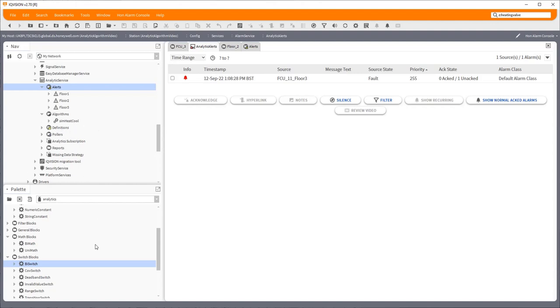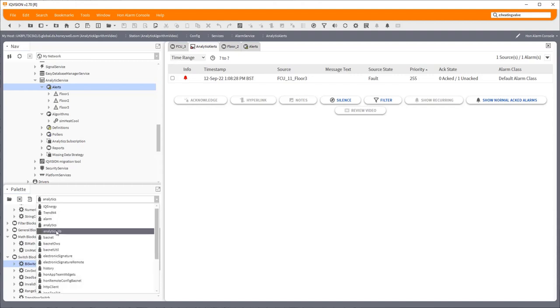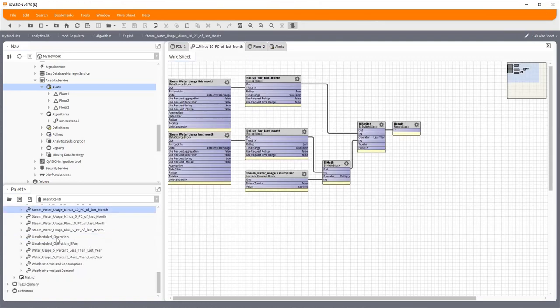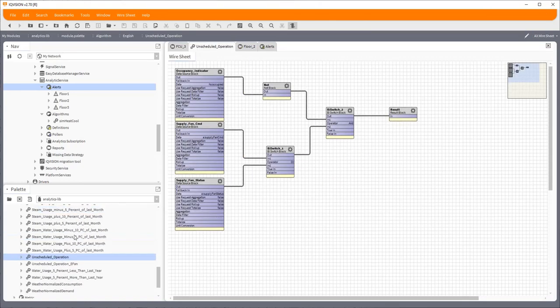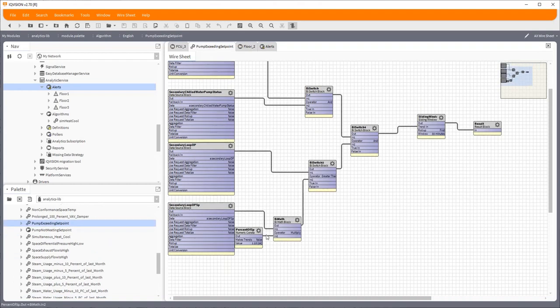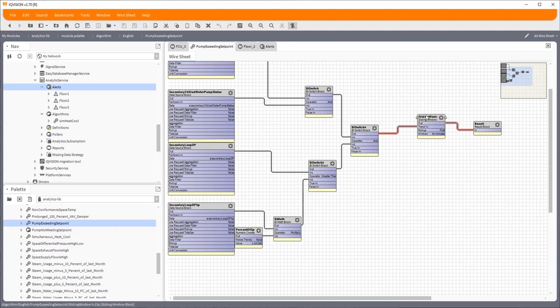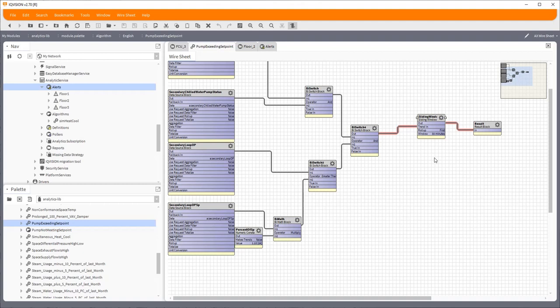So I hope that is of some use. There are some 50 odd examples in the analytics library. You can use these as you see fit. You can see how they're all assembled, and hopefully the little demo I've just given you will give you some idea as to how these pieces actually all slot together. One piece I will specifically mention is a sliding window, very useful but quite difficult to give you a demonstration about it without us hanging around waiting for 30 minutes for something to go wrong. So if I wish to use that, for example if I wish to time that both the coils are open for longer than 10 minutes, then I would have the results feeding into this sliding window to just basically check my understanding. And I could do that too with the stuck valves, so if they're at anything over 50% for longer than an hour, let's say, we could say that that is perhaps stuck. So the sliding window is an incredibly useful block to have in there.